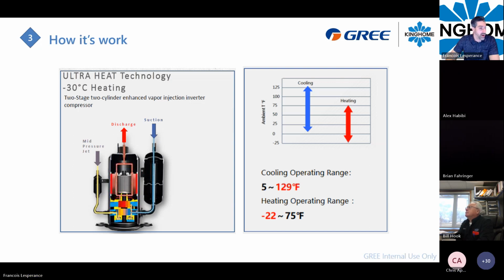Perfect. I have a question as well, if you don't mind. Yes, go ahead. You were mentioning that you have 2 outdoor condensers, a 3-ton and a 5. Yep. When you said the 5 goes down to a 4-ton, what are you doing for the 3.5-ton unit, or the same thing on the 1.5? There is no half-ton with this kind of unit, but through the fine-tuning at the end of the presentation, I will explain how to do it. Okay, thanks. No problem.